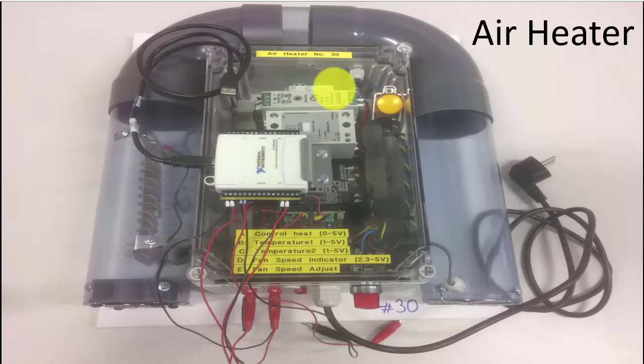When this is up and running, and we have found some proper PID parameters we can use on the simulated process, then we can go to the next step, where we replace the PID controller we have used in software with the real hardware, in this case the real Fuji PID controller, which we will use to control the same mathematical model. So then in this case we need to use the DAQ device. And then when we are able to control the mathematical model using the real hardware, then we can finally test the hardware on the real process or the real plant like this. And in this case, you also don't need any DAQ device. Just connect the process directly to the PID controller like this.